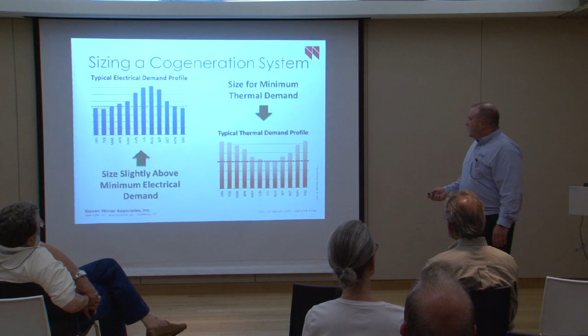This explains where utility prices stand right now. If you're a building in New York City heating with gas, you might pay around $1.20 a therm, and around 20 cents per kilowatt-hour for electricity — that's the box you're in buying from the grid. A cogen unit lets you buy electricity at a much lower rate, around 8 to 10 cents per kilowatt-hour. Buying natural gas at the preferred cogen rate and converting it to electricity generates power at around 8 cents, versus the 16 to 24 cents you're paying now depending on the season. The cogen gas rate stays steady throughout the year and doesn't fluctuate.